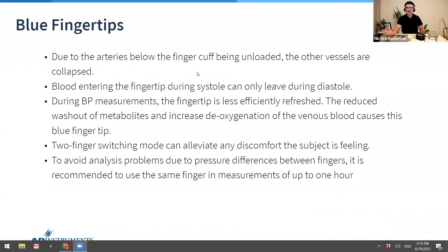Finally, with the system itself, as we are constantly increasing and decreasing the cuff pressure and keeping the unloaded diameter in the arteries, other blood vessels around these arteries will be collapsed. What this does mean is that the blood entering the fingertips during systole can only leave during the diastole phase. During BP measurements, the fingertip is obviously not sufficiently refreshed, therefore metabolites increase, and also we see an increase in deoxygenation. Hence, you may see some blue fingertips, which will lead to some discomfort over, say, half an hour to 1 hour. So generally when it gets up to 1 hour, we would recommend switching from one cuff to the second cuff. That's the whole point of that. That way we can go for long-term studies.